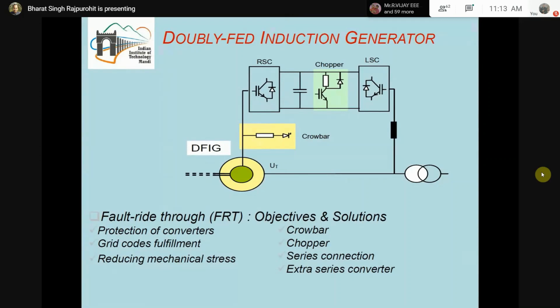Now coming to this line side converter. The line side converter has a role to maintain the DC link voltage constant, because as the rotor side converter is either feeding the power or taking the power out, the DC link voltage is going to change. So the main role of this line side converter is to always maintain this DC link voltage. So it means taking the power out from this DC link or injecting power into the DC link, in both directions of power flow. Power can be extracted from the grid or can be injected into the grid. So this is the role of this line side converter.